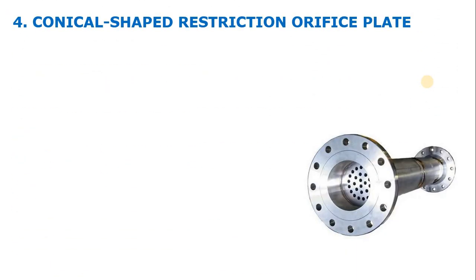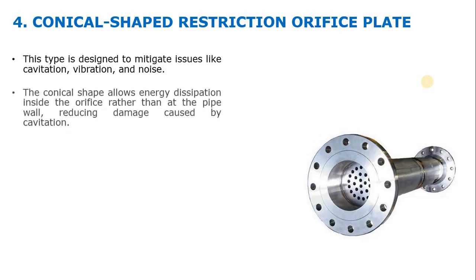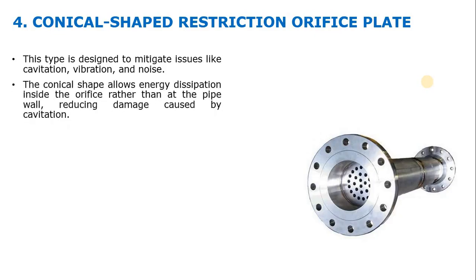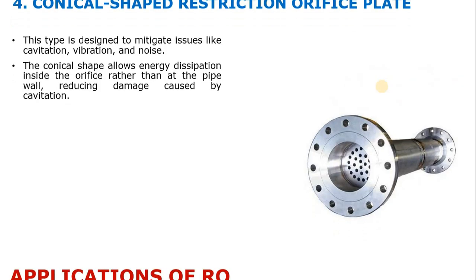There is also the conical shaped restriction orifice, which is designed to mitigate issues like cavitation, vibration, and noise. It transitions from a larger size to a smaller size — for example three inch to two inch — so one side is bigger and the other side is smaller.